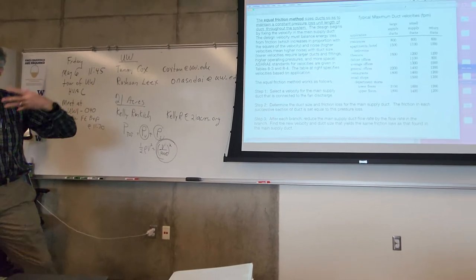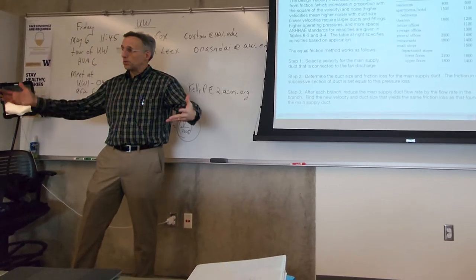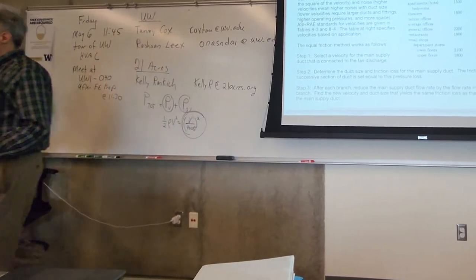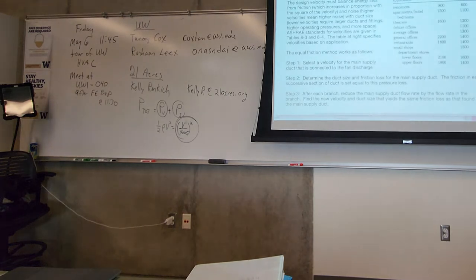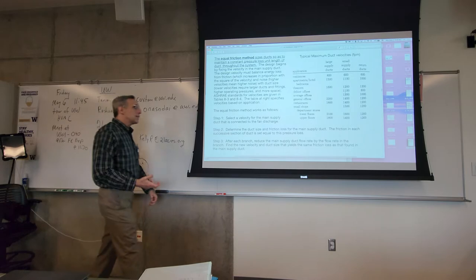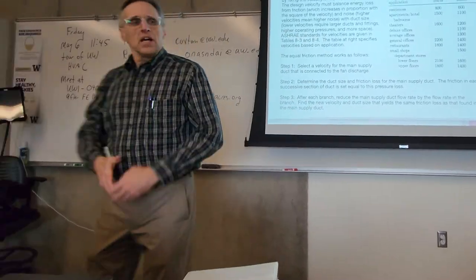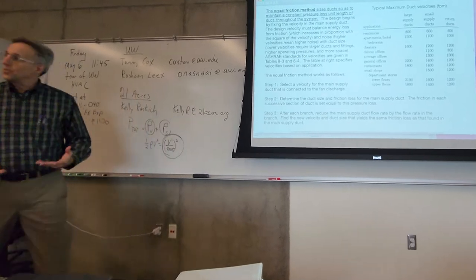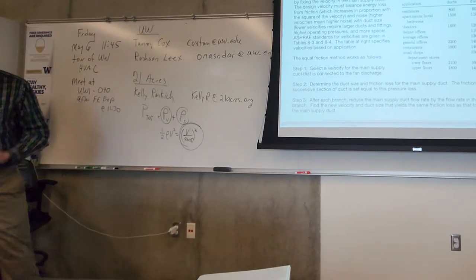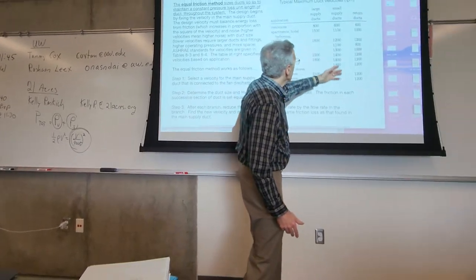And I know what the CFM is because I've already done my psychrometric analysis. So we figured out what my supply air condition has to be, right? We know what the Q is, QS, right? We already did that. So we know our CFM. Now I want to know, okay, how fast do I need to push this CFM through my ductwork? Usually it's going to be between 1,000 and 2,000 feet per minute, maybe 900 feet per minute. And you can sort of see that range here.